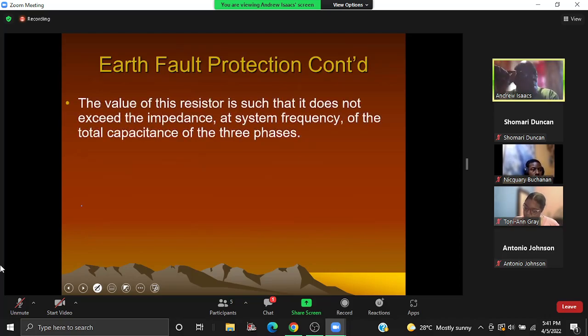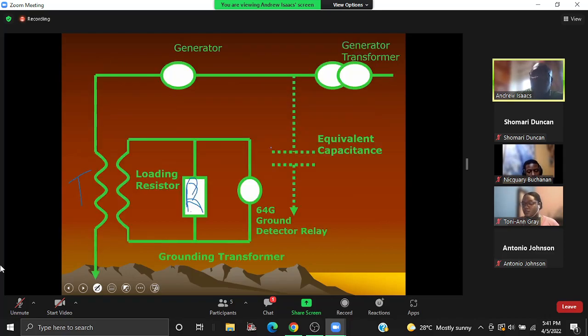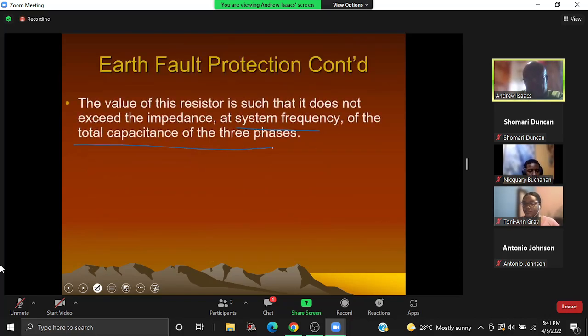So the value of the resistor that we have there is such that it does not exceed the impedance at system frequency of the total capacitance of the three phases. All right, so we have some leakage capacitance here. And that total capacitance is made up of, well, there are several considerations for that leakage capacitance. So the resistor is such that it does not exceed the impedance at system frequency of the total capacitance of the three phases.